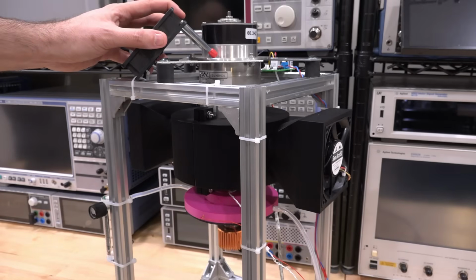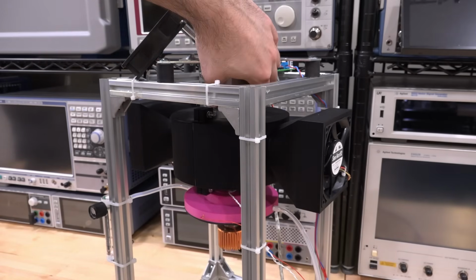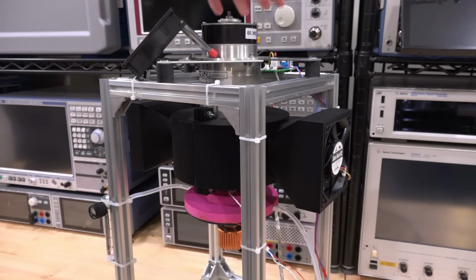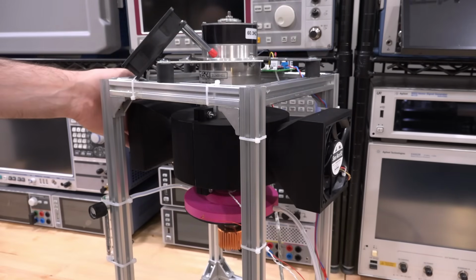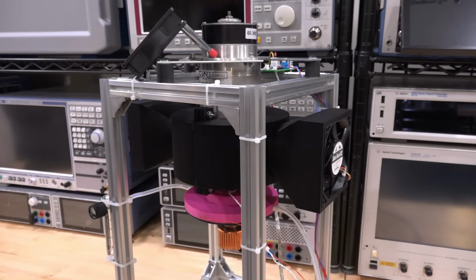And there's a fan here at the top that blows across the body of the cryo engine itself, and that's going to cool the electromagnet and everything else, trying to lower the temperature of this as much as possible. Now, in order for these fans to not run at 100% all the time, there's also a temperature loop that I have created, which I will show you, so it runs them at a reasonable speed. Essentially only runs them as fast as it needs to.